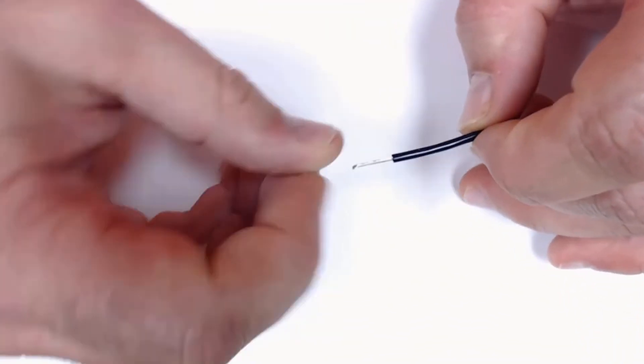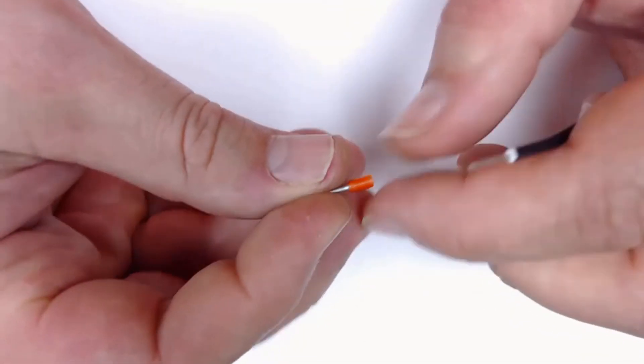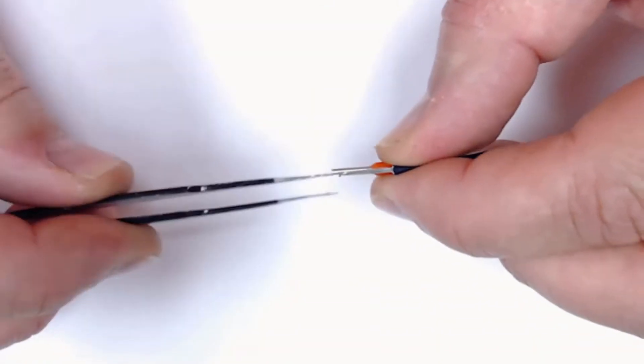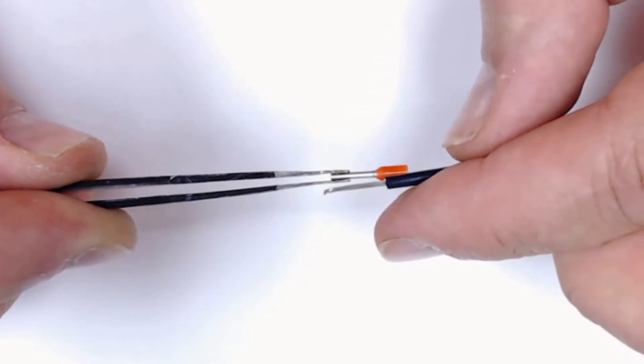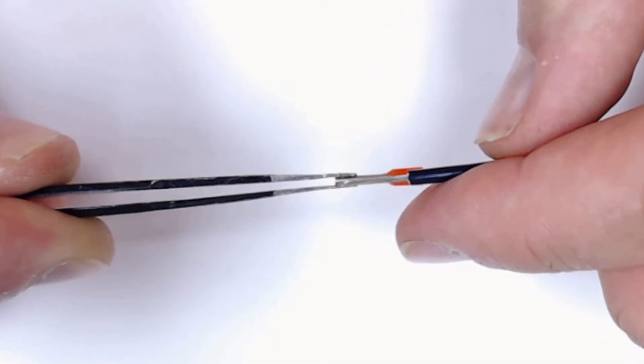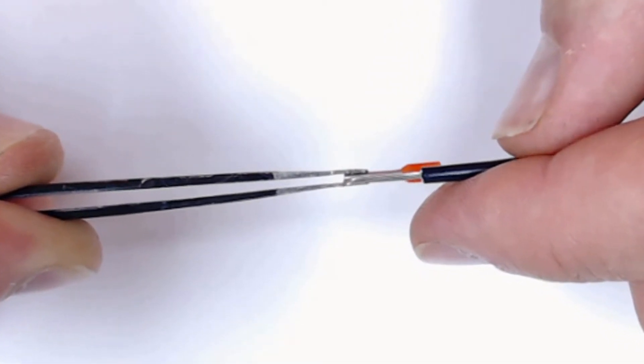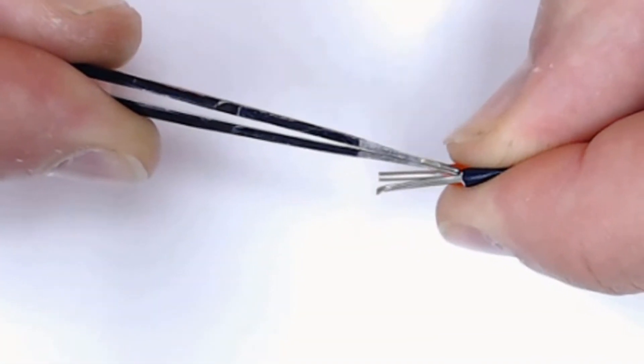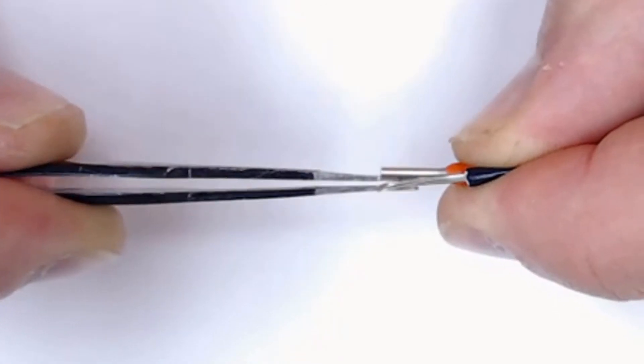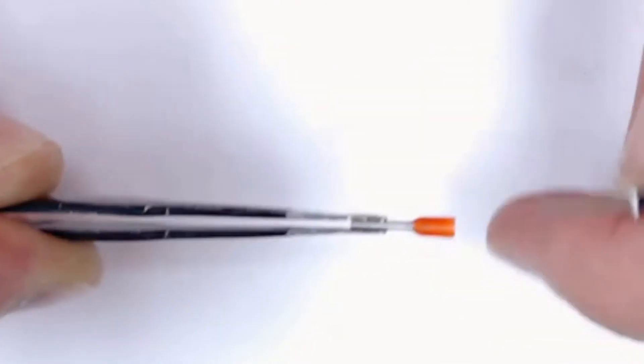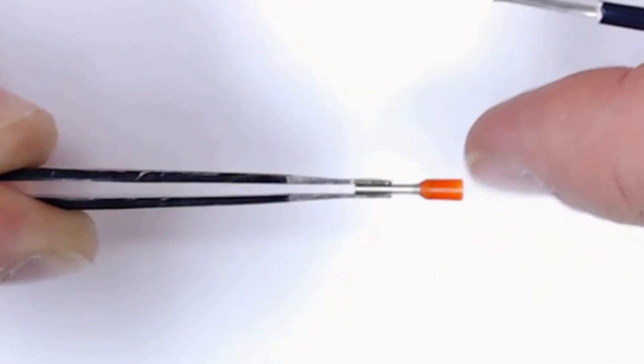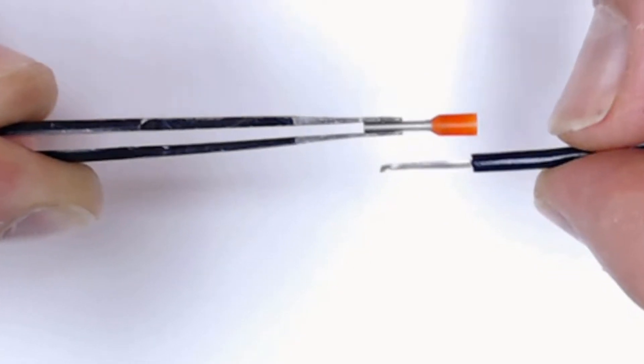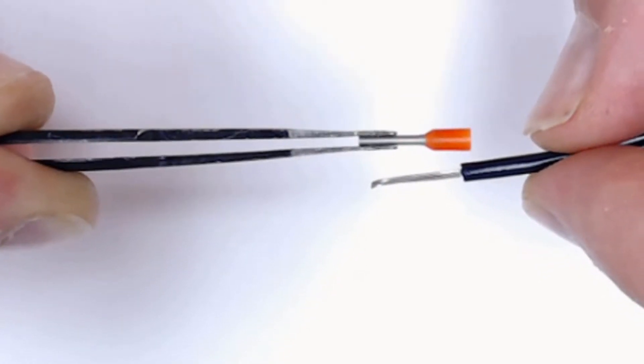Now that we have our wire stripped back, we want to make sure that our strip length is correct. What we're going to do is hold this up next to the ferrule. As you can see, when we're flush with the ferrule, we've got a little bit of extra wire here. That's okay, because the shroud around this ferrule is going to cover up that extra wire and also engage the insulation.